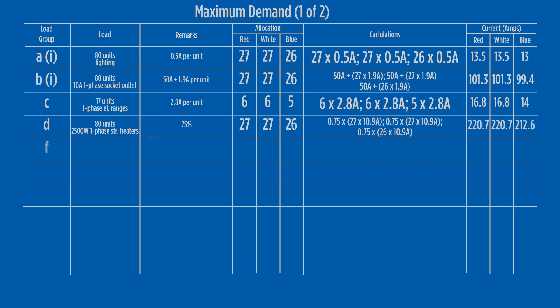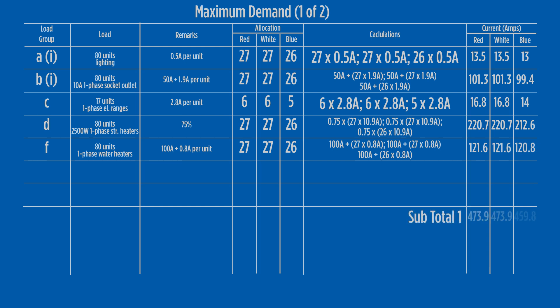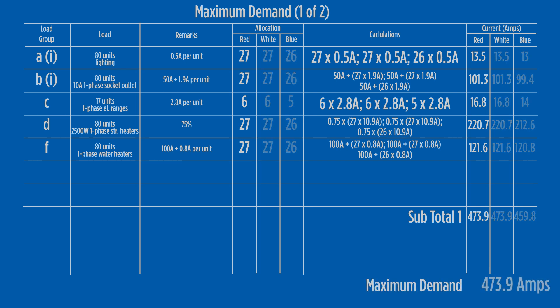Load group F allows 100 amps plus 0.8 amps for each hot water system per unit. The calculation for hot water systems comes to 121.6 amps. At this point, the loading associated with individual units is complete. The maximum demand value sits at 473.9 amps.